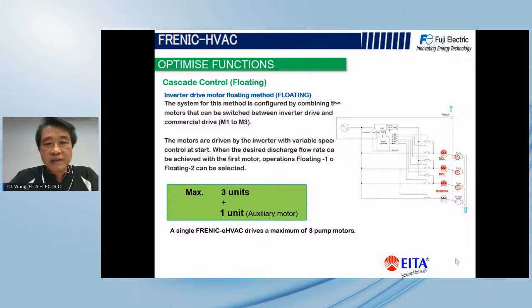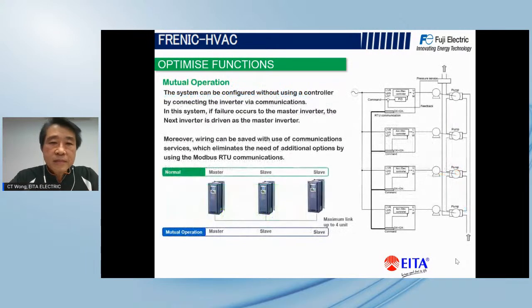You can see that today inverters are getting smarter on this. And we also have mutual control. The difference is that just now you needed hard wiring, but today the inverters can interface and communicate with each other, as master and slave. Basically the master will run. If the master reaches maximum and still cannot fulfill the demand, it will call for the second pump to come in. What about if the master fails? As I say, the slave will take over as master. So you can see that with this technology, the energy savings will come in.